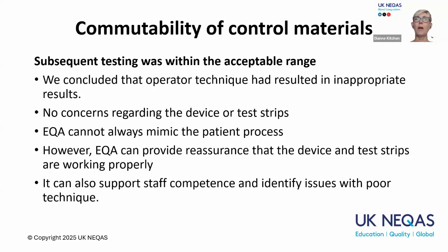Since that time, I've had a little look at this centre and they're doing well, results within acceptable range. So we concluded from this that the operator technique had resulted in inappropriate results. We didn't have any concerns regarding the device or test strips, but it does highlight that EQA can't always mimic the patient process. The problem was the operator not following the instructions, and the feedback I had from her when I spoke to her was that she didn't have time to read the instructions. She just threw it together and tested and hoped for the best. And that's not a very scientific approach.